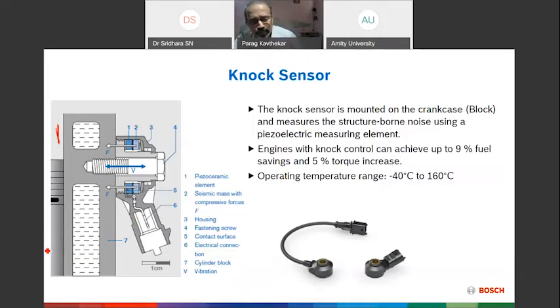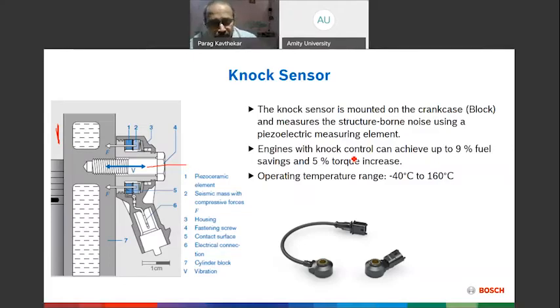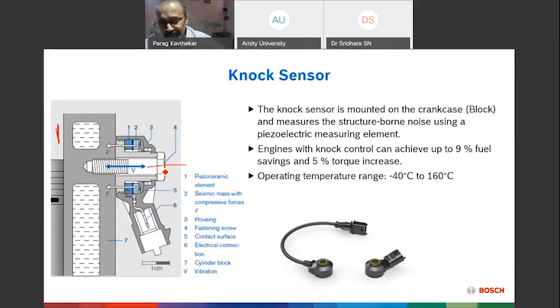One thing: the 4-number fastening screw or bolt is fixed with a torque wrench. If we fit without using the torque wrench, it may get over-tightened and may start producing a signal at a normal combustion rate also. So based on this fastening torque, it starts producing a signal at a normal level also. It is very difficult to identify what the problem is, where the problem is. So a torque wrench is required to fasten this bolt, because the element inside, 1 number and 2 number, is fitted based on that torque value. So caution is required when fastening the bolt wherever it is used.